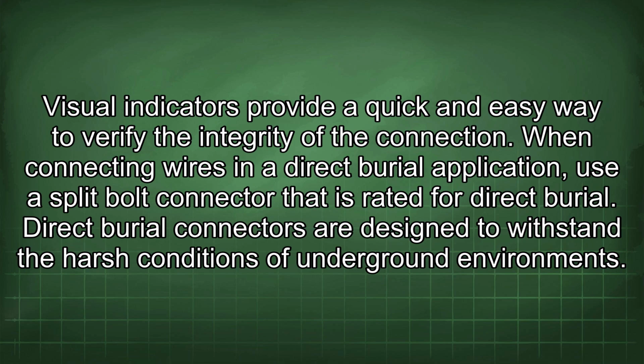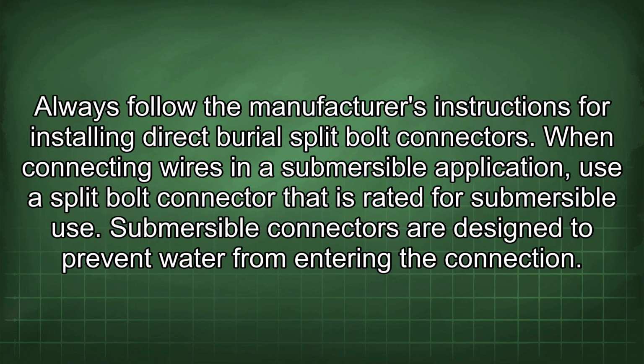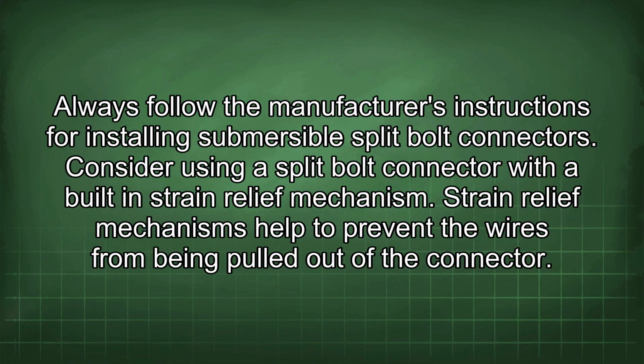When connecting wires in a direct burial application, use a split bolt connector that is rated for direct burial. Direct burial connectors are designed to withstand the harsh conditions of underground environments. Always follow the manufacturer's instructions for installing direct burial split bolt connectors. When connecting wires in a submersible application, use a split bolt connector that is rated for submersible use. Submersible connectors are designed to prevent water from entering the connection. Always follow the manufacturer's instructions for installing submersible split bolt connectors.